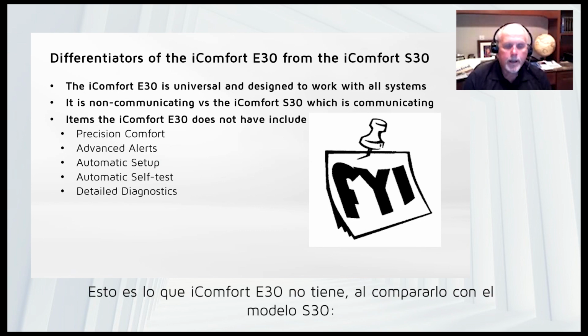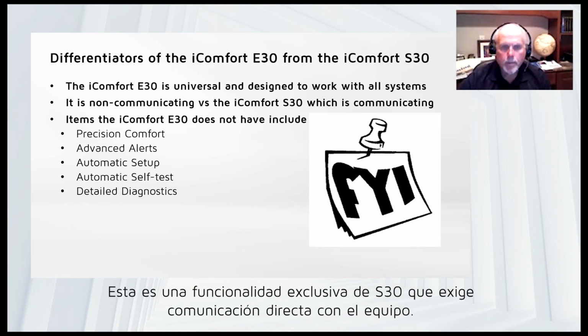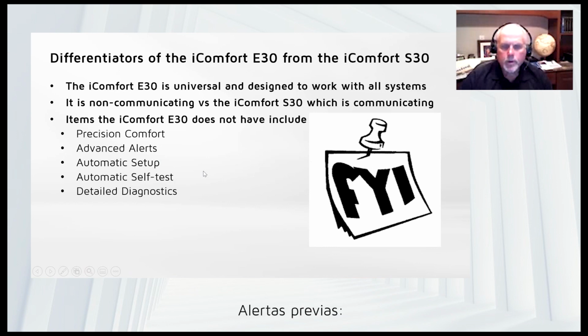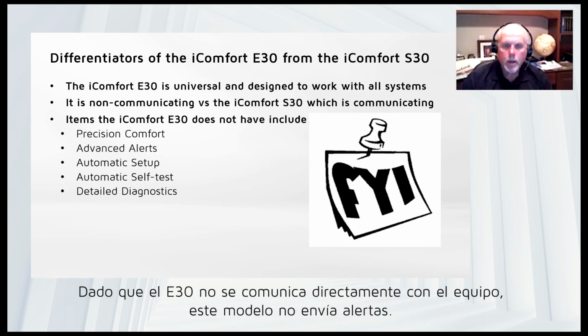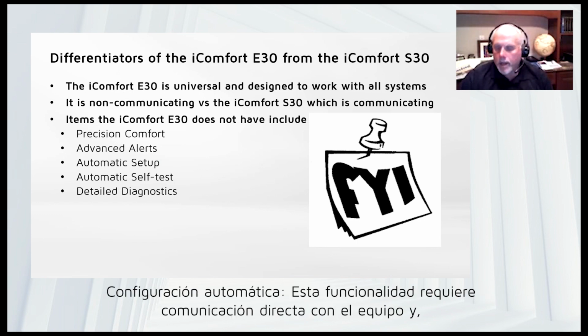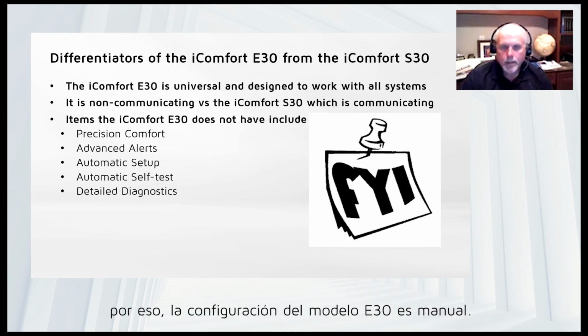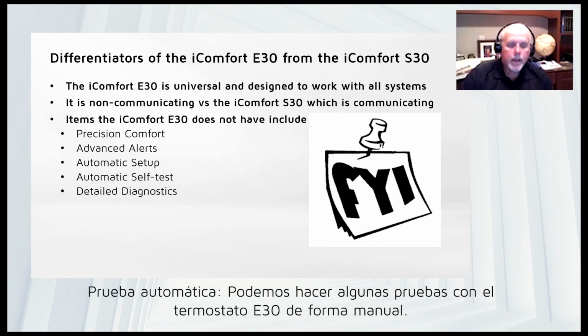Okay, the items the iComfort E30 does not have versus the S30. We have these 5 things here. So precision comfort. That is a setting with the S30 because it communicates directly with the equipment and can operate the equipment to achieve precision comfort. Advanced alerts: since the E30 does not communicate directly with the equipment, we do not get any alerts. Automatic setup: with the S30, it communicates with the equipment, so it knows what's out there. It knows the size and so forth. So it sets itself up, where the E30, of course, is not communicating with the equipment and cannot do that.